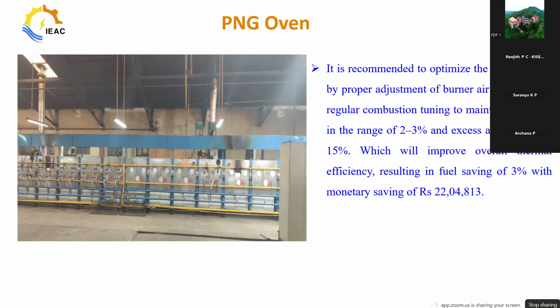So we use an equipment known as a flue gas analyzer, which correctly measures the air content, oxygen content, nitrogen, and other components like CO2, NOx, O2, etc. Each of these has to be calculated separately, and from that we can determine whether the combustion is proper, or whether the air is properly mixed with the fuel.